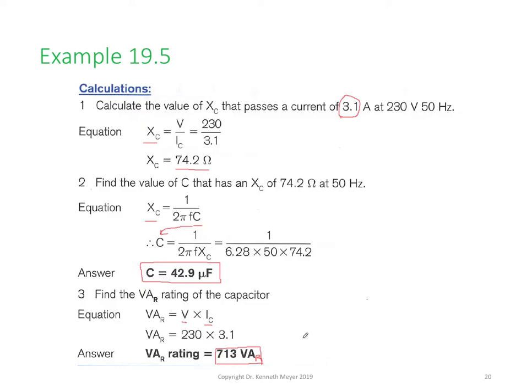So volts amps reactive. So we did a scale drawing. We found out what our current would be required for our capacitor. And then we used some Ohm's law to work out the capacitive reactance. Then we used our reactive formula to then work out the size of the capacitor we would need, and then simply to work out what the VAR is. It's the voltage multiplied by the current through the capacitor tells us the volts amps reactive.